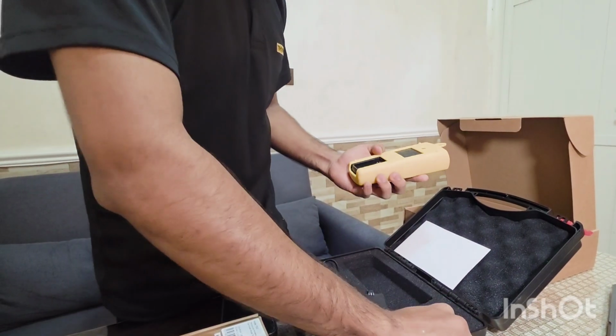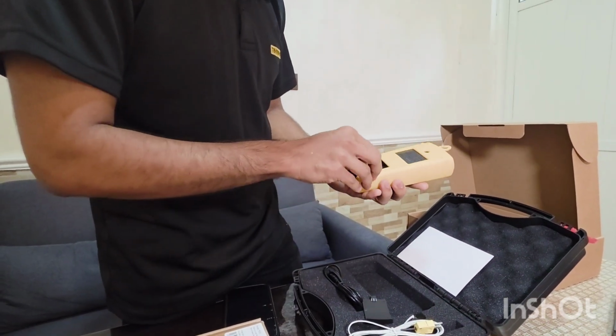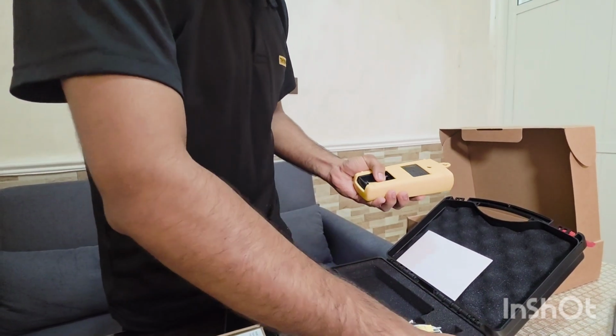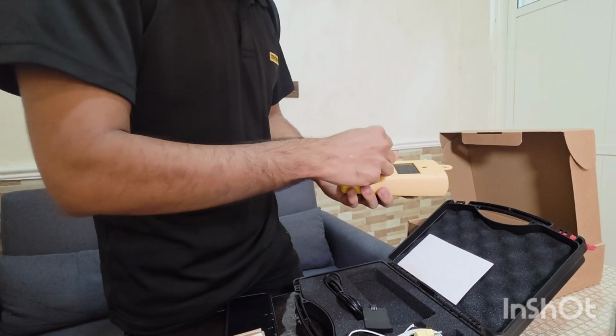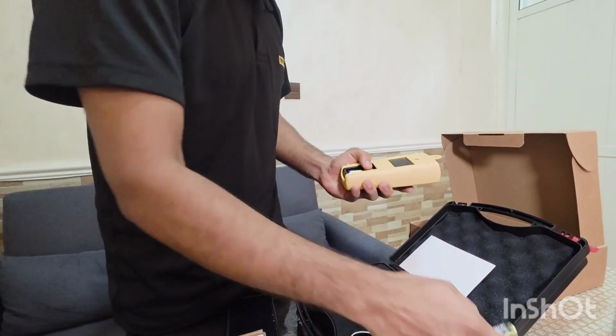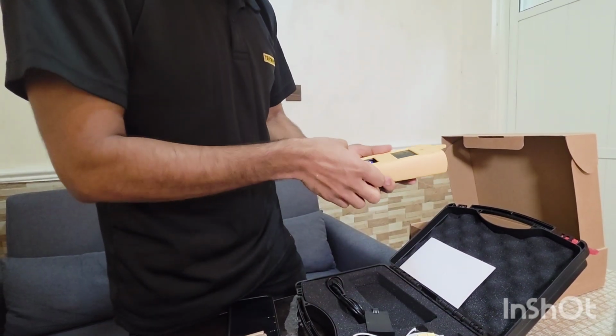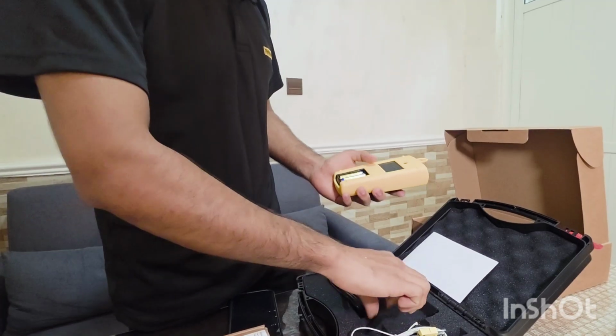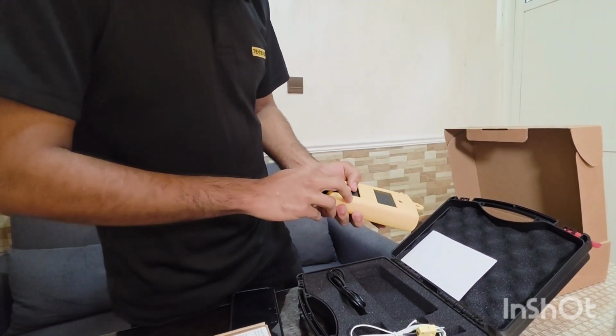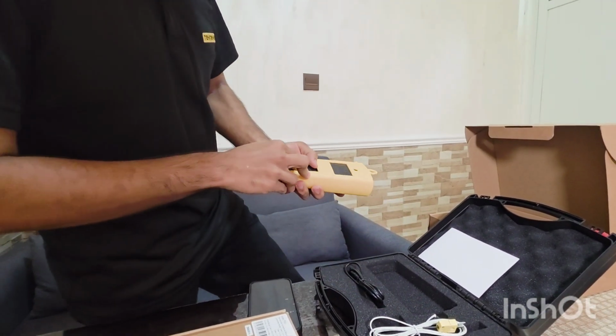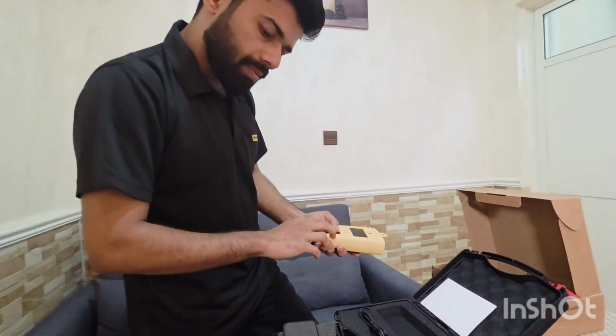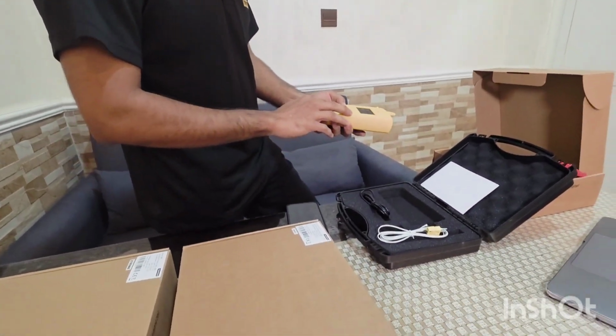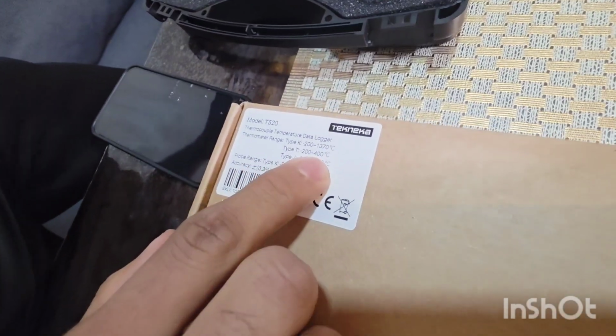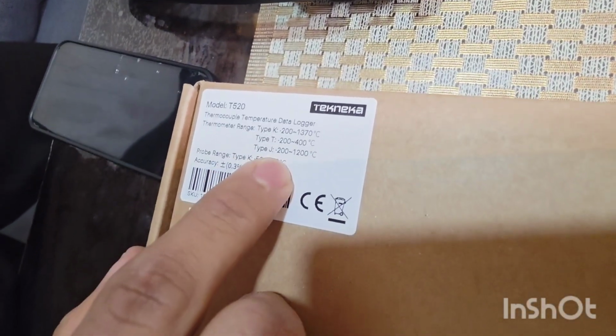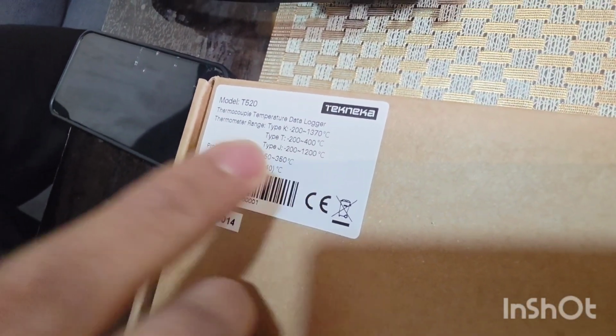Let me put the battery. And all these data loggers are capable of measuring different types of thermocouple, which is, you can see, type K, type T, and type J. Type K measures from -200 to 1370, type T measures from -200 to 400 degrees, and type J from -200 to 1200 degrees.